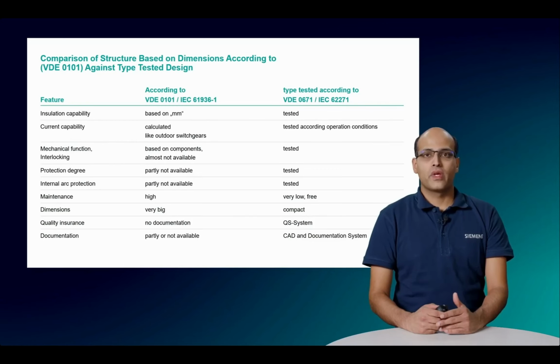In the past, the interlockings were based on components used in design and almost not available. Today, these are tested as per standards. The same can be said for protection degree, which were only partly available in the past days, but are type tested at present. Another important thing is the protection against internal arc, which relates to the personal safety. The modern day switchgears are type tested to ensure that they are internal arc classified as per IEC standards.